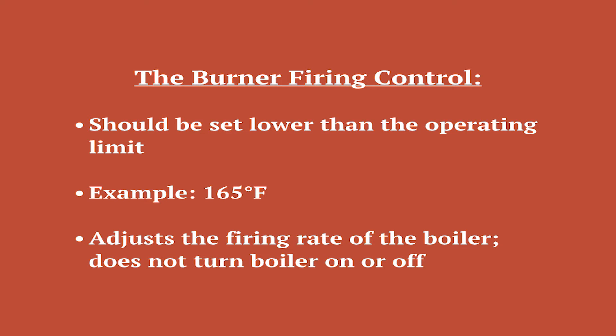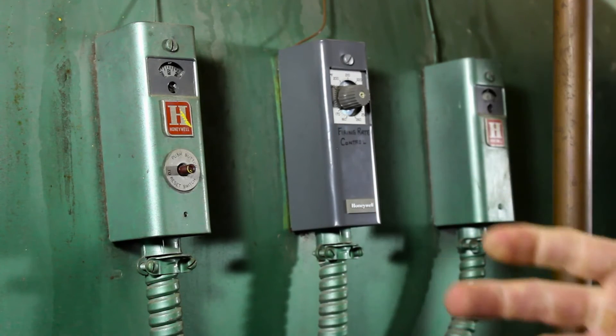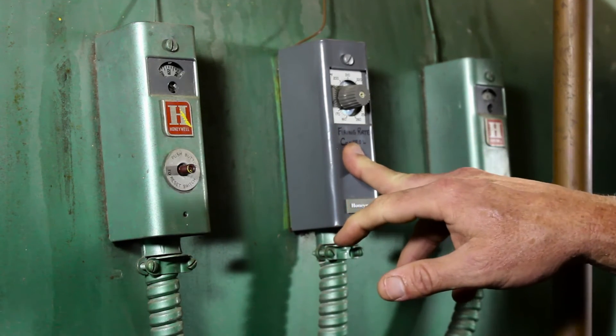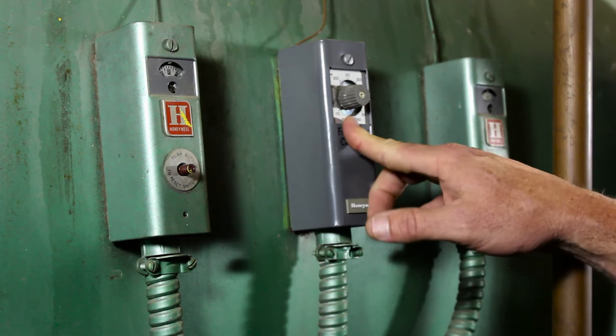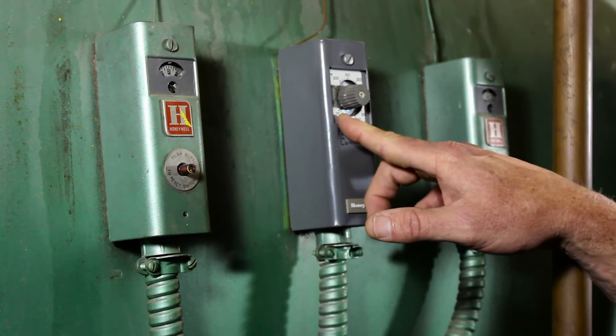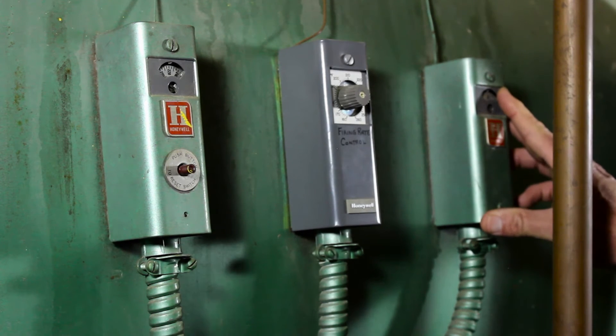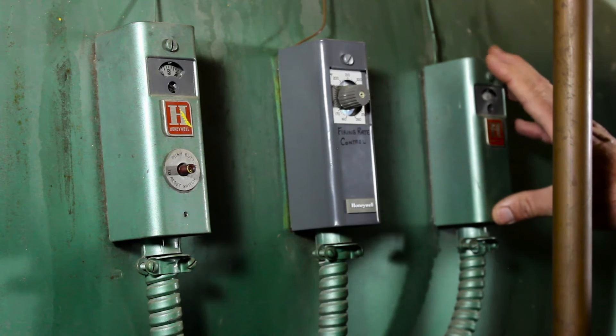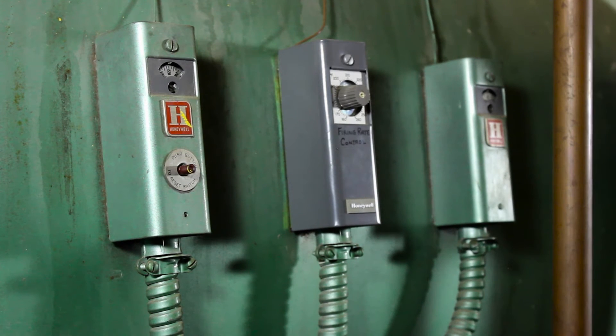What this controller does is control the modulating percentage of your burner to accurately control the water to the set point. This one is set at 165. So what happens is, when the boiler is called to engage, the firing rate controller takes over and tries to maintain a water temperature of 165. If the load in the building isn't high enough and even at minimum fire the water temperature continues to rise above 165 and gets to 180, then the whole boiler will shut off. There's a differential inside this controller that's usually 15 degrees, so when it gets down to 165, the cycle will start again.